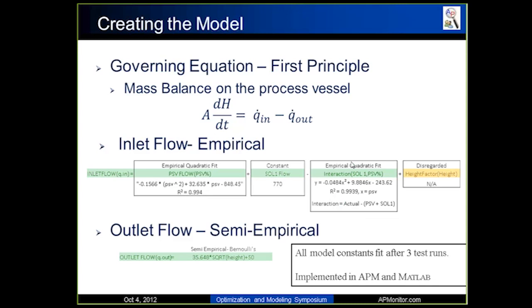And then I have this other term, which is called an interaction parameter, because there's something interesting that happens: if you turn the discrete valve on and the PSV on, it doesn't actually equal the actual flow rate. It doesn't combine to that. So I made this interaction parameter that determines what is the true flow rate. Basically, the interaction is equal to what the actual flow rate is minus this one together. And so with this model, I was able to accurately predict what is the true inlet flow rate into the actual process.